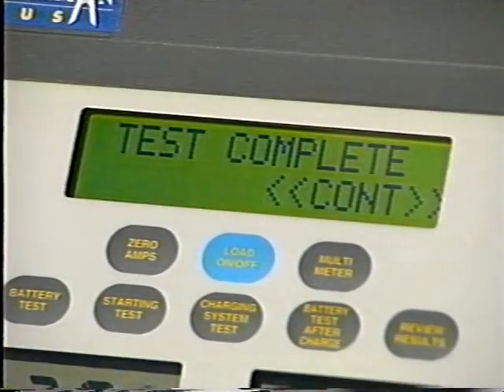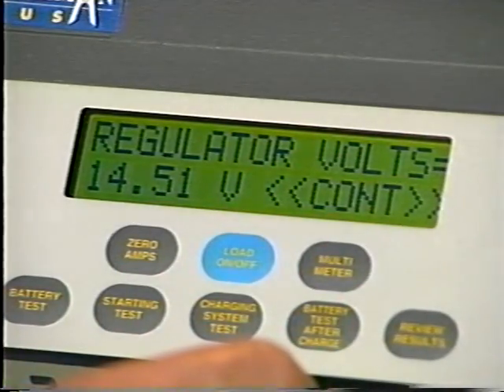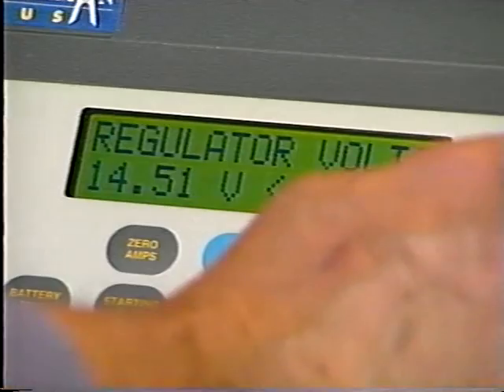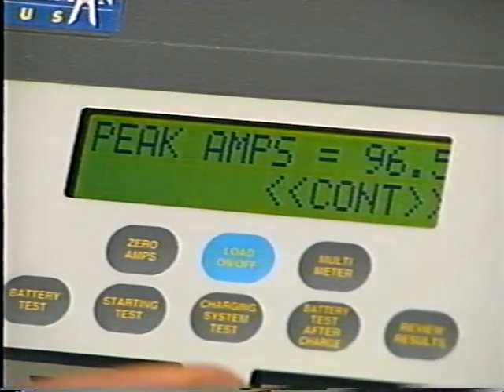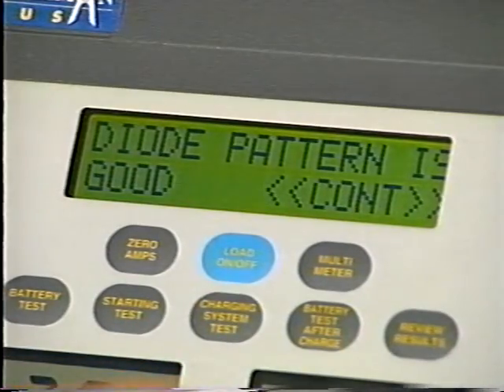When the test is complete, press Continue to review the test results. The first value displayed will be regulator volts. Press Continue again to view peak amps. Press Continue for a third time, and the Minuteman will tell you if the diode condition is good or bad.